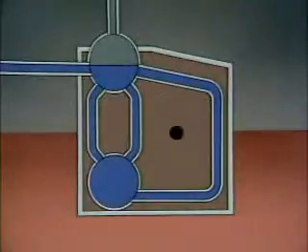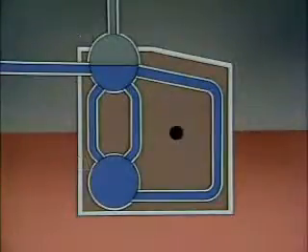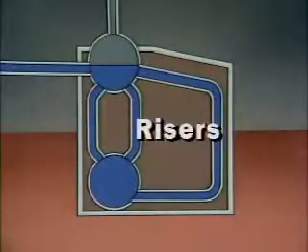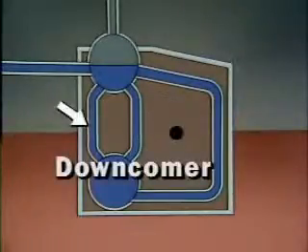For a boiler to produce steam, water has to flow through the boiler properly. One way to provide water flow is by a process called natural circulation. In a simplified water tube boiler, there are two drums: an upper steam drum and a lower mud drum. A series of water tubes called risers carry a steam-water mixture to the steam drum, and a downcomer carries water from the steam drum to the mud drum.